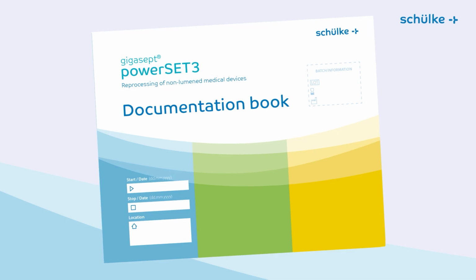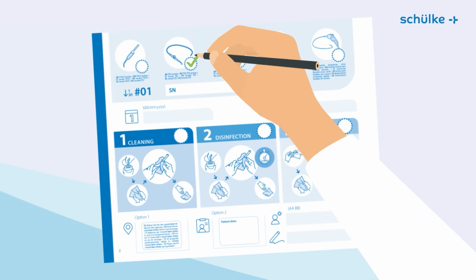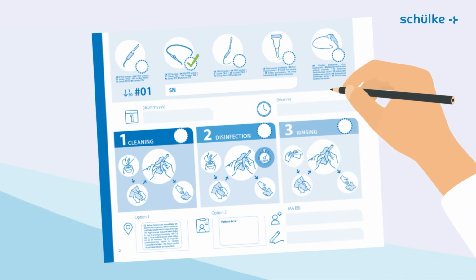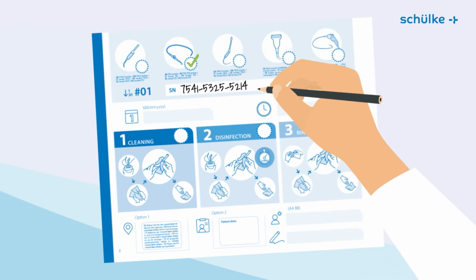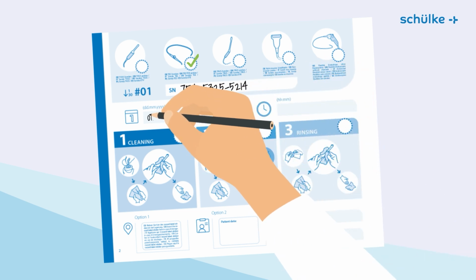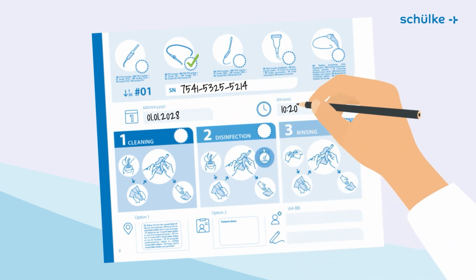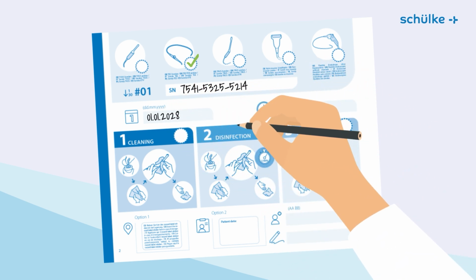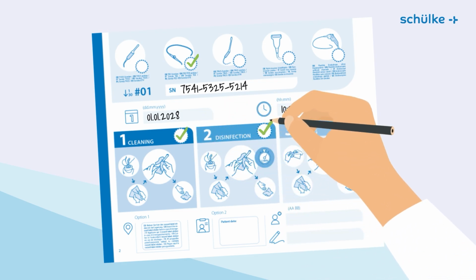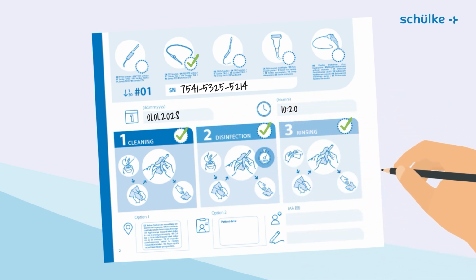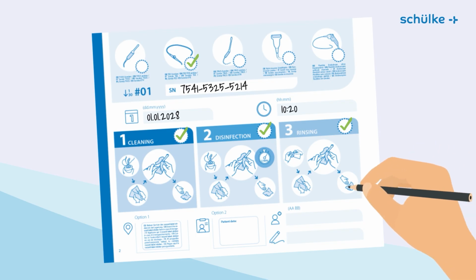Please do not forget to complete the documentation in the enclosed booklet to ensure full traceability. Select the medical device that has been reprocessed and note the serial number or another unique identification number. Enter the date and time of reprocessing and tick the boxes for the successfully completed reprocessing steps. If the medical device is to be stored after reprocessing, take a record label sticker from the enclosed sticker sheet and put it in this field.